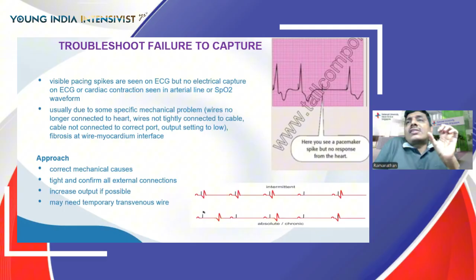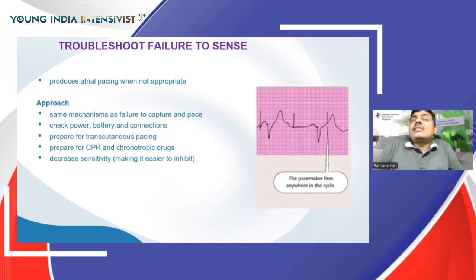Now, one other thing that can happen is the ability of the pacemaker not to sense. So here, the pacemaker fires anywhere in the cycle, and it produces, let's say, atrial or ventricular pacing when it's not appropriate. This can be dangerous. It can lead to R on T. So you'll have to do the same kind of general principles that we spoke about. Look for all these things as we did with the previous two troubleshooting. And as I said, you might have to prepare for other modes of pacing, maybe even prepare for CPR, sometimes even decrease the sensitivity so that it's easier to inhibit.